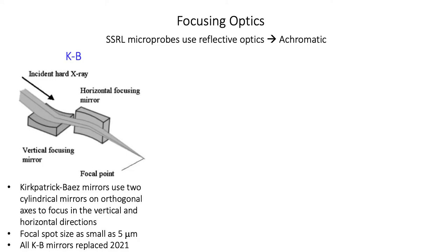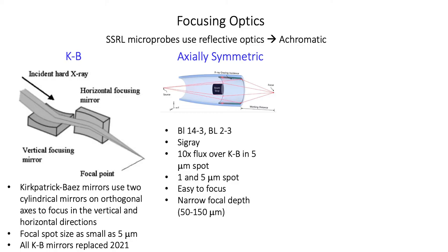All of SSRL's microprobe beamlines use reflective optics, which are achromatic — meaning we can use the same optic across a very broad energy range spanning thousands of eV. All of our SSRL beamlines used to have KB mirrors, or Kirkpatrick-Baez mirrors, which are commonly used at micro-XRF beamlines around the world. This system utilizes two cylindrical mirrors on orthogonal axes to focus the beam vertically and then horizontally, obtaining a spot size as small as five microns.